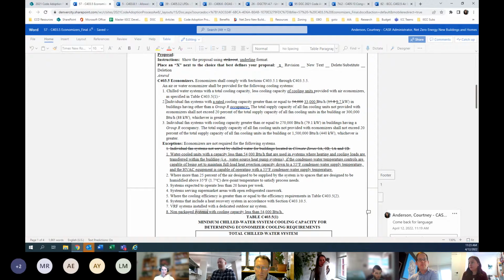True, and total capacity. Just being devil's advocate, if a building designed a bunch of mini or small split systems that exceeded 300,000 BTU, we're not exempting that by creating this exception, are we? No, I don't think so, because there's still the overreaching code where once your whole building exceeds a certain cooling capacity, you also trigger the economizer requirement. So this would be like little buildings that fall beneath both—a little office or fitness center—and I'm forgetting what the whole building threshold is, maybe 40 tons. I can't remember, but your supermarket wouldn't be able to have 40 different split systems and not trigger the economizer requirement.